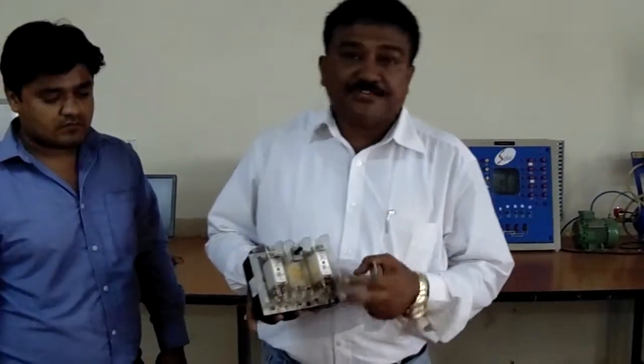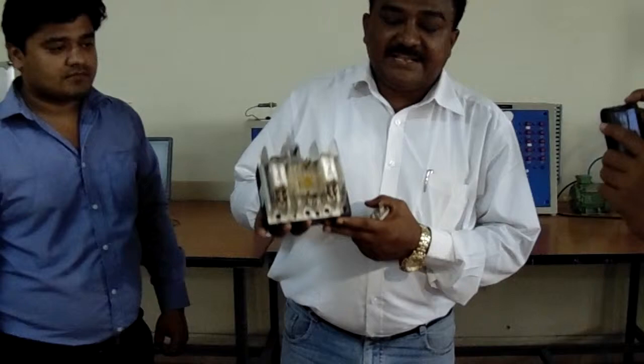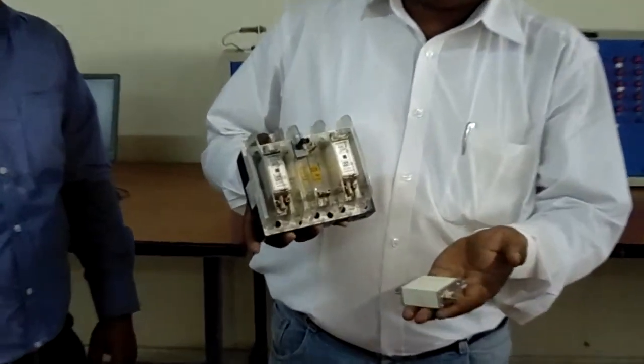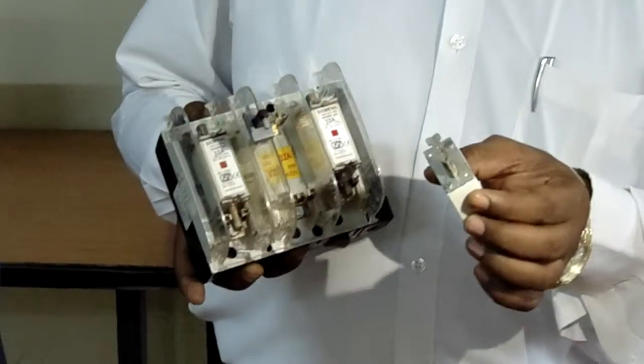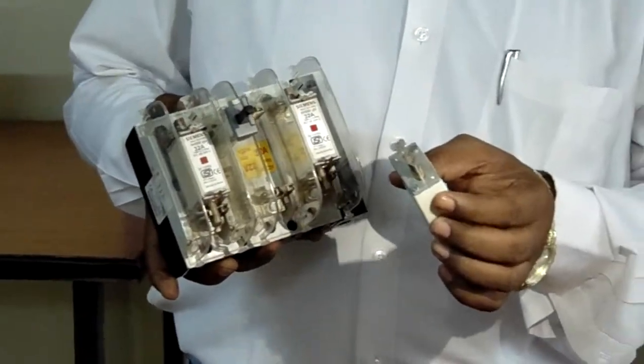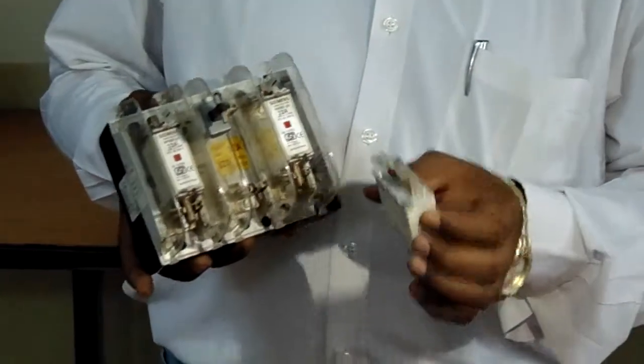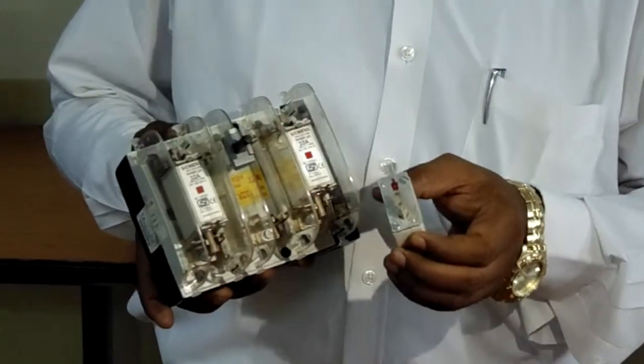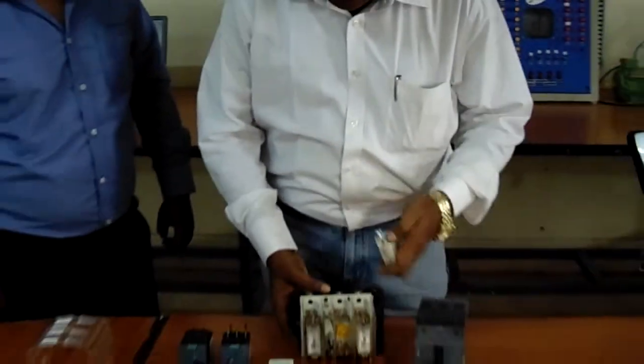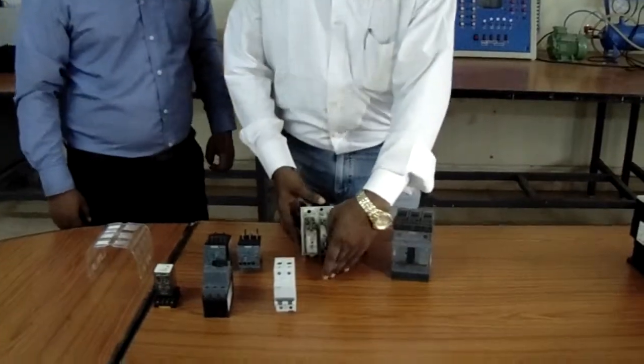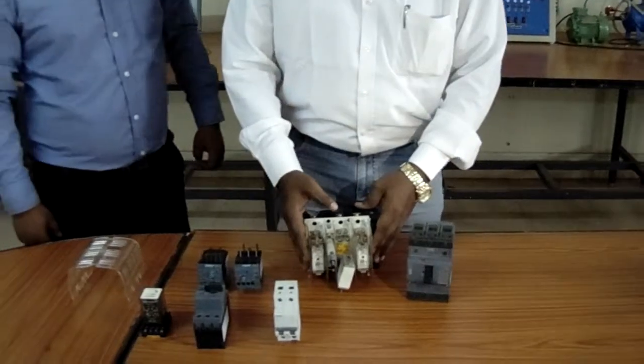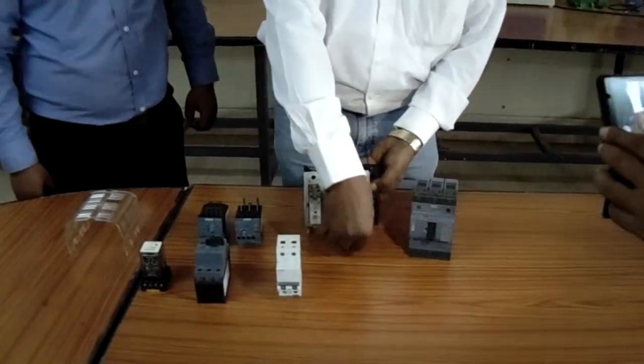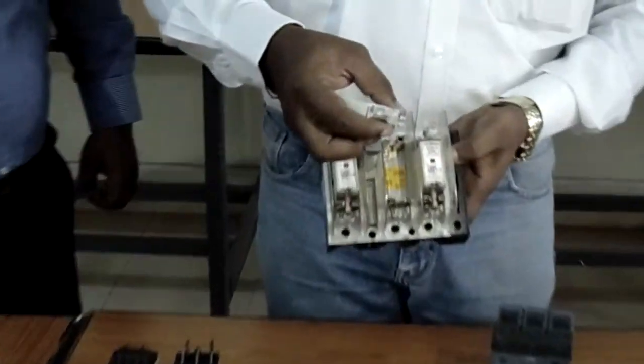This switch fuse unit consists of a base and fuses. Normally, whenever there is a problem in the electrical circuitry, this fuse is going to blow off. And when the fuse blows off, we have to replace this fuse with a healthy one. Normally, for lower current ratings, these switch fuse units are not used. The switch fuse unit consists of a base, fuse and a rotary handle.